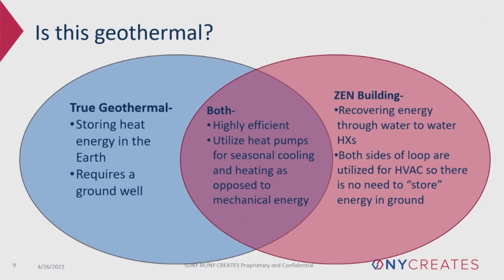At this point, you might be wondering how this project is geothermal. And you would be correct to ask that because technically it's not, by true definition, a geothermal project. We don't have any ground loop. We're not rejecting heat into the Earth's surface. Instead, the Zen building utilizes energy recovery through heat exchangers, sophisticated controls, and water source heat pumps so that both sides of the loop are needed and there's no need to store energy. Instead, it is harvested immediately by other equipment either needing heating or cooling.